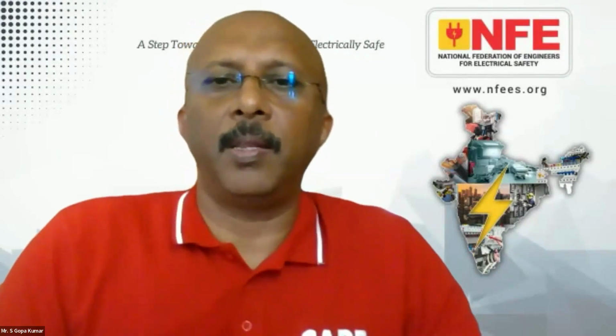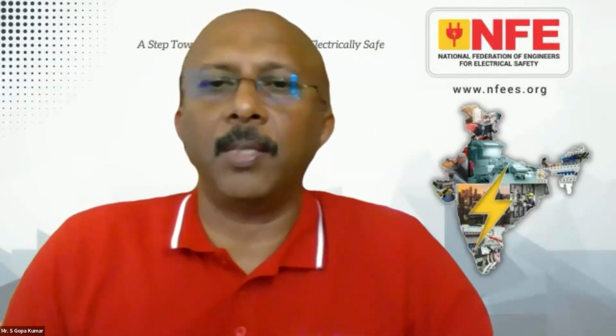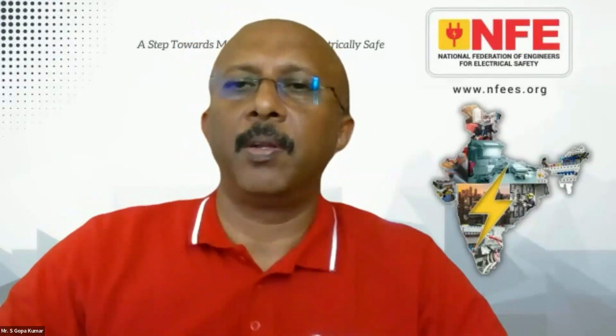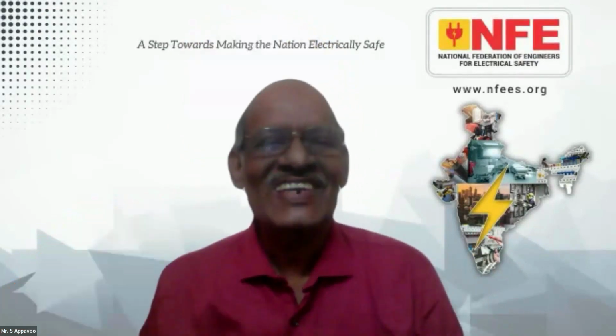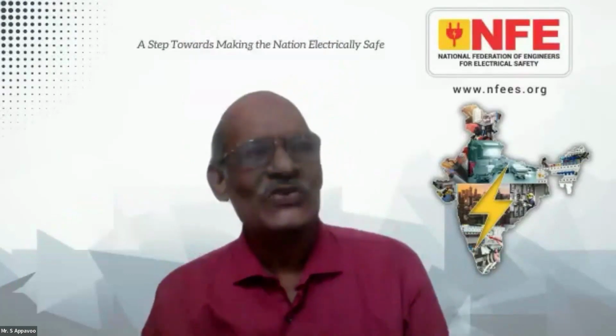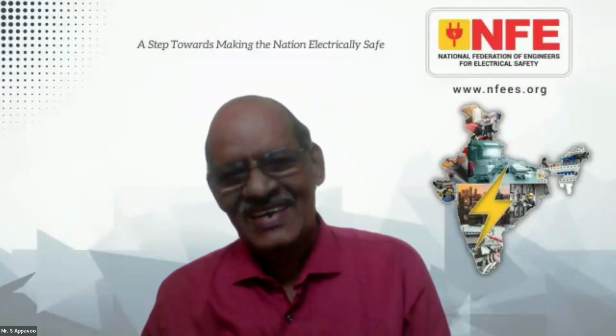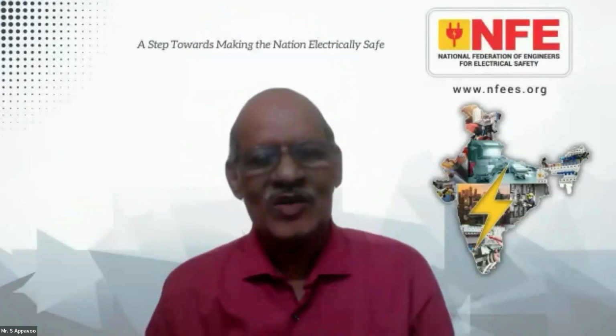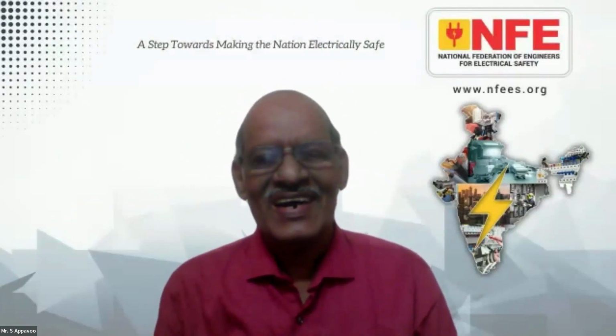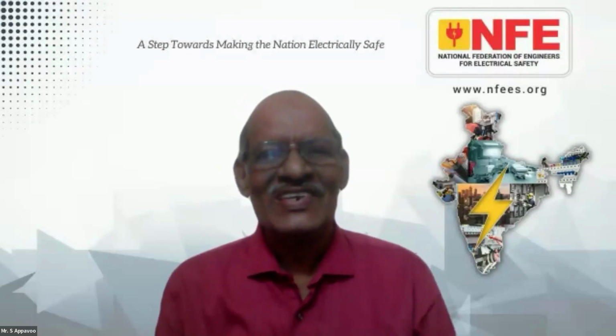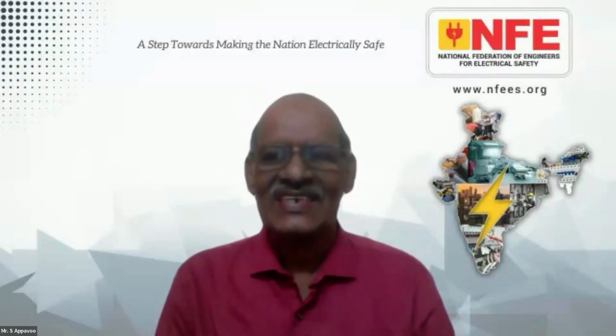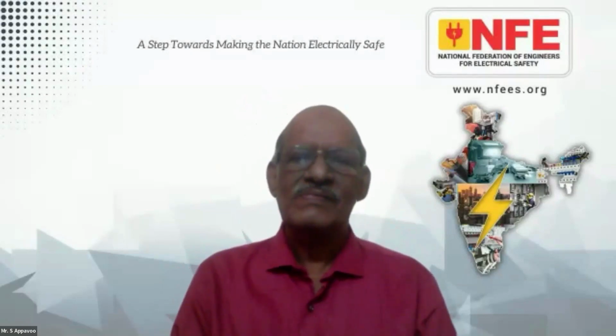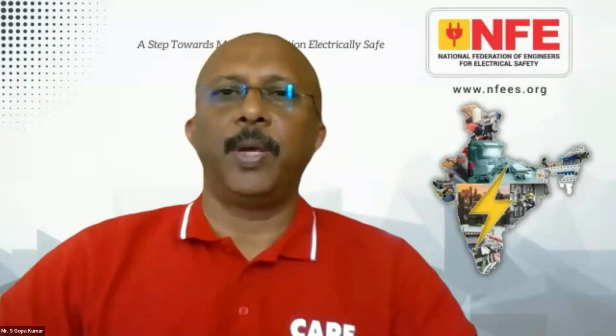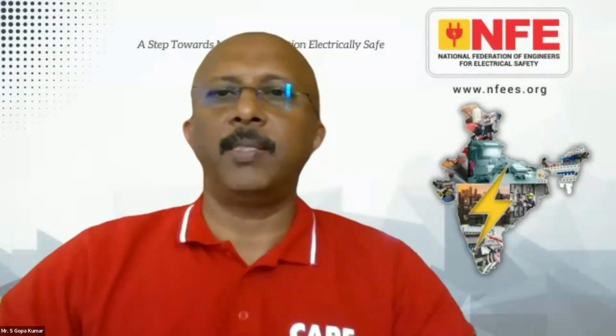So, sir, again, another question from Mr. Smritiranjan. Can we connect a lightning arrestor to the neutral earthing of a distribution transformer? I have given, as per IEC 60099 Part 5, one slide: bad, good, and very good. You adopt that very good system. You have to interconnect. Yes.